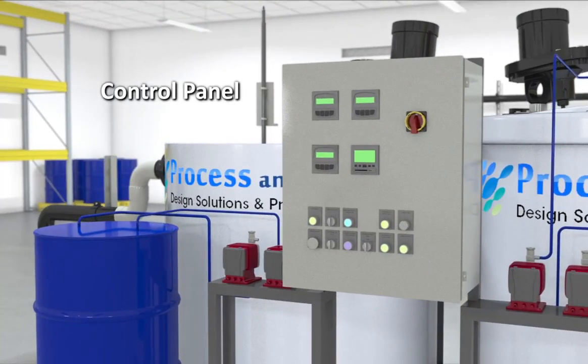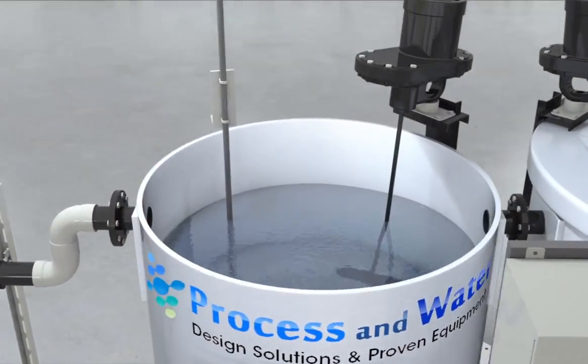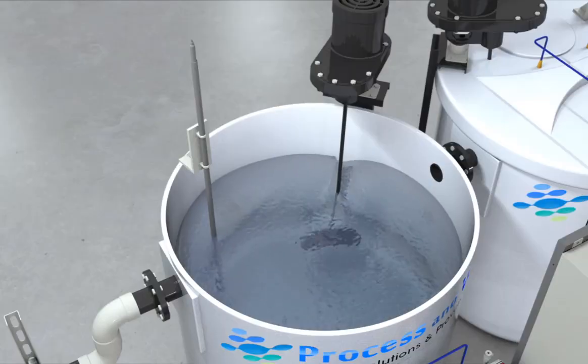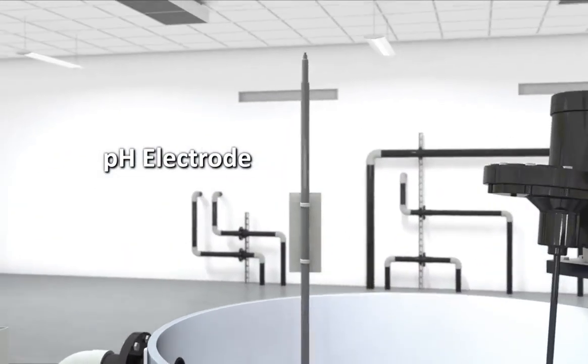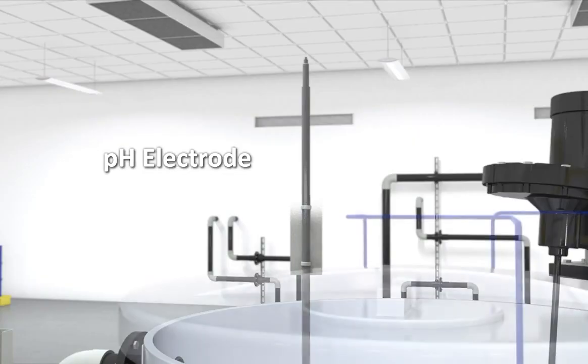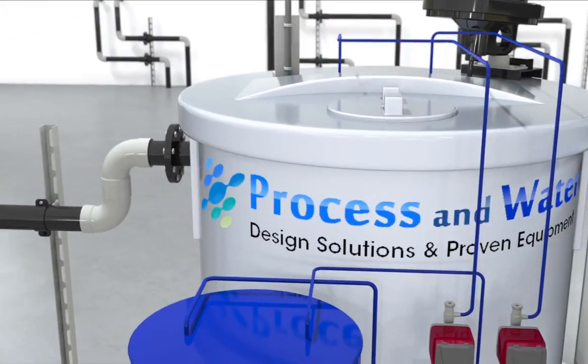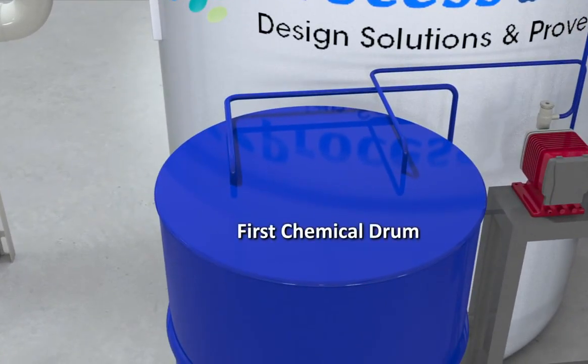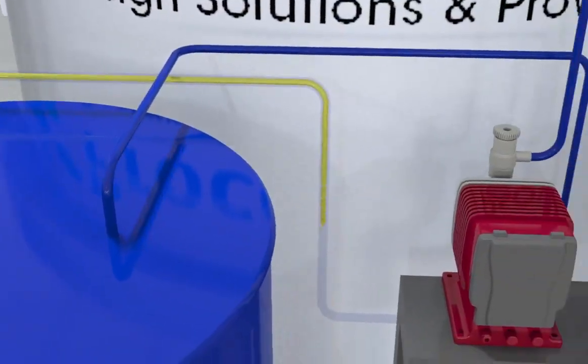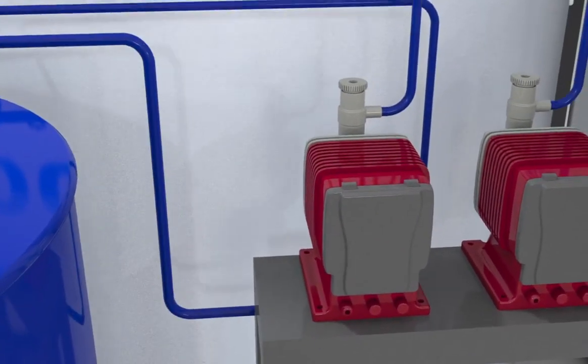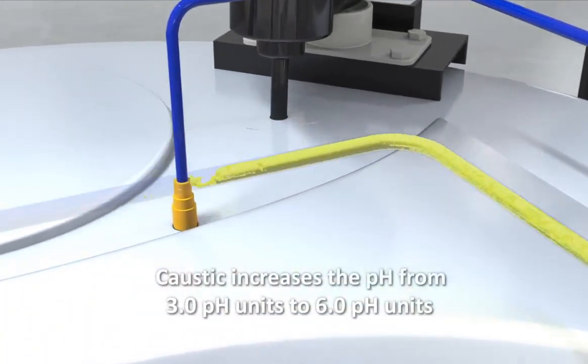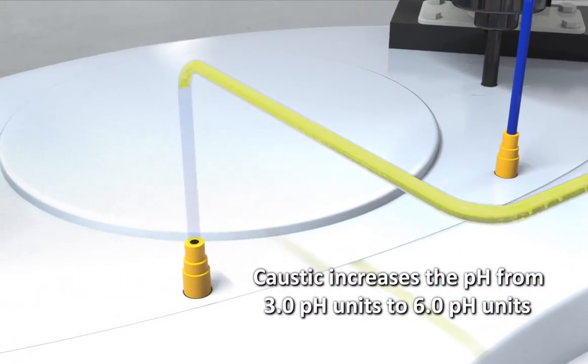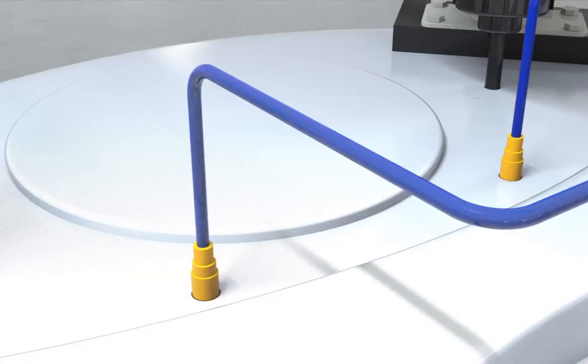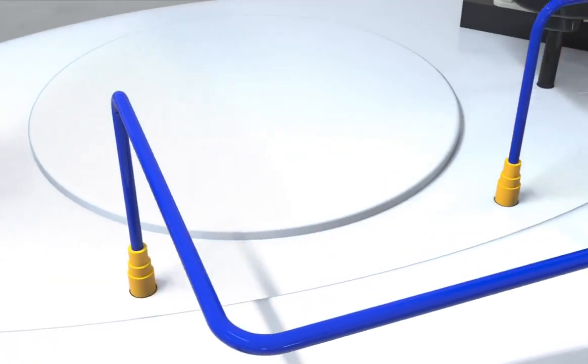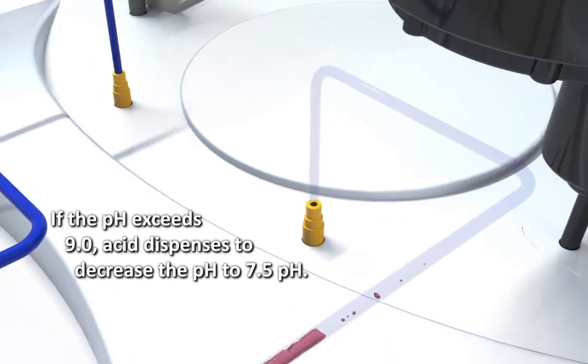Using the control panel, an operator may begin the mixing process, agitating the water. The pH electrode senses the pH and displays the results on the control panel. The chemical metering pump dispenses caustic from the first chemical drum through the metering pump to the tank to increase the solution's pH from 3.0 pH units to 6.0 pH units. In the event the pH increases to over 9.0 pH units, the acid dispenses to decrease the pH to 7.5.